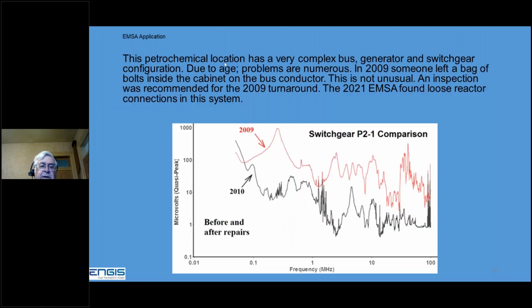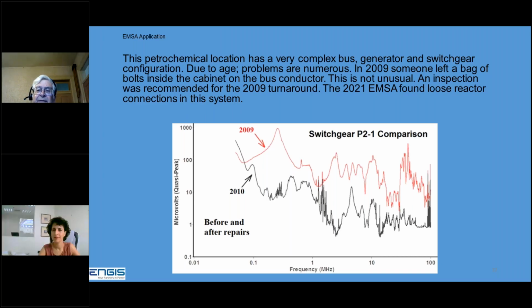This is a petrochemical site down in Louisiana. We've been testing there for almost 20 years. It is a very complex bus system. They have several generators. They have several buses. They have series reactors to limit fault current so the breakers will work. It is getting 40 years old, so there's a lot of problems.